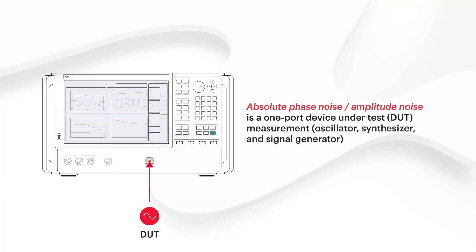Today we're going to show off three of these measurement capabilities. First we're going to measure absolute phase noise. This is the measurement of a one-port device like a signal generator, a synthesizer, or an OCXO. David will show off the absolute phase noise of our highest performance vector signal generator, the M9484C VXG.